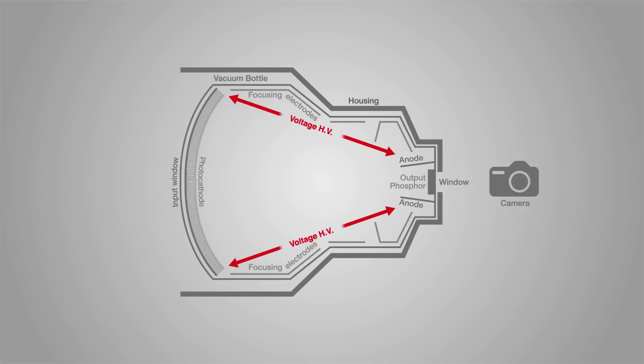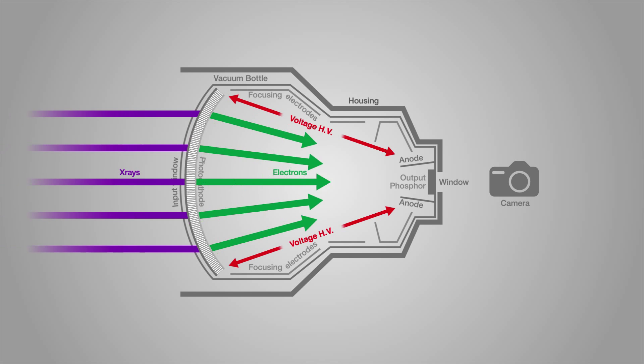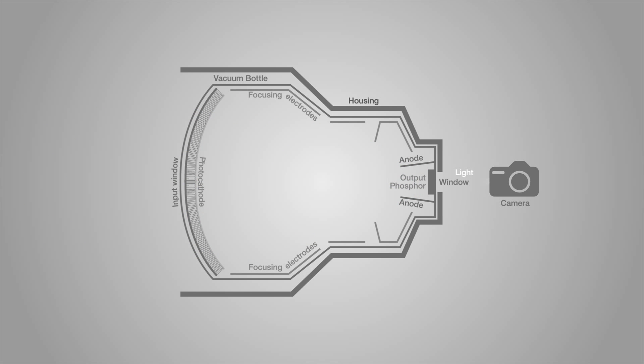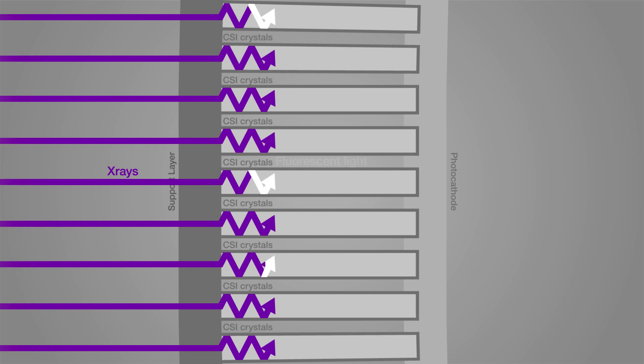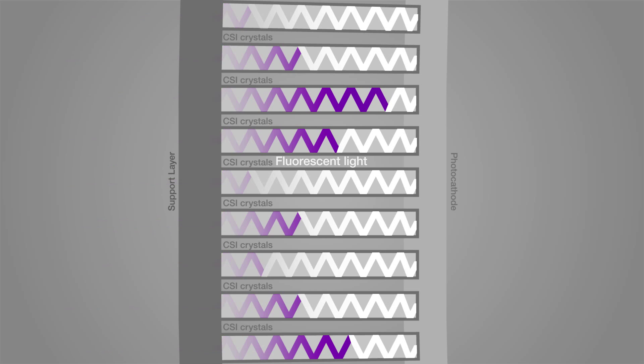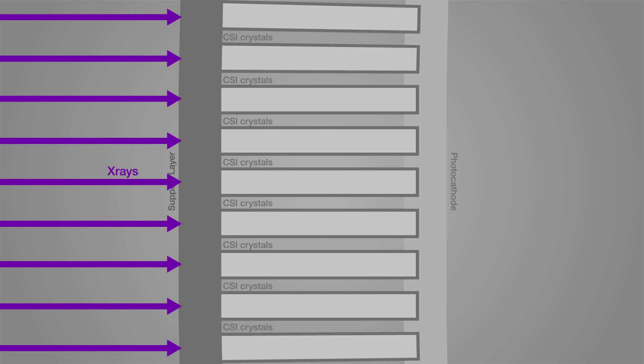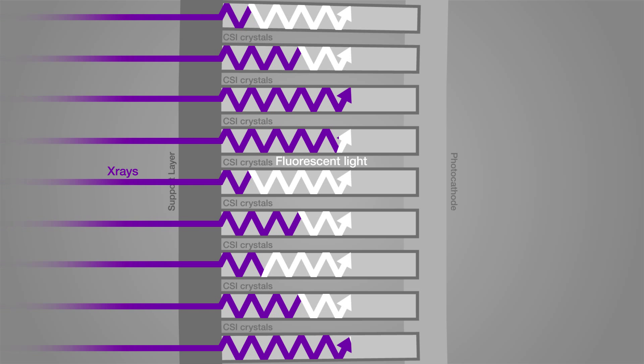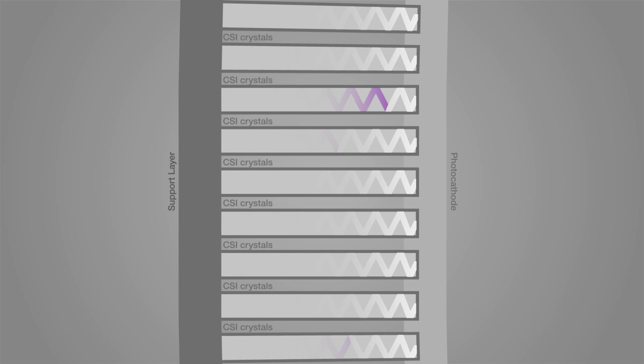Let us now look more closely at the input stage. Here we see the X-rays entering the scintillator cells, in this case caesium iodide, where they are converted to photons at the frequency of visible light.